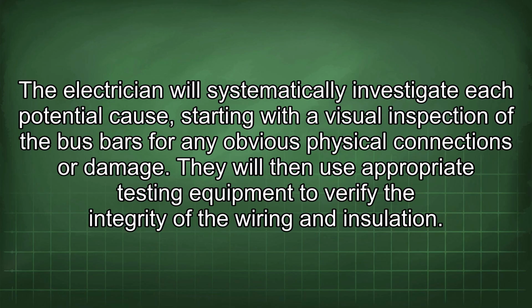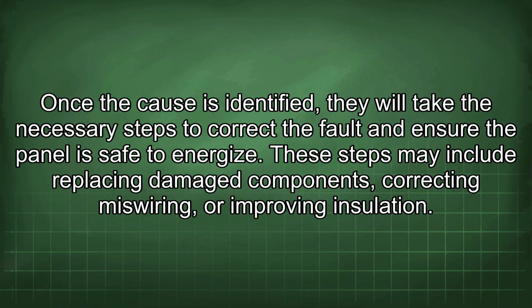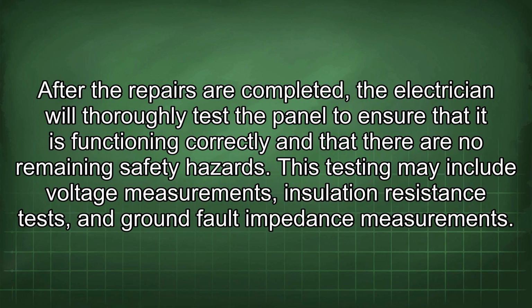The electrician will systematically investigate each potential cause, starting with a visual inspection of the bus bars for any obvious physical connections or damage. They will then use appropriate testing equipment to verify the integrity of the wiring and insulation. Once the cause is identified, they will take the necessary steps to correct the fault and ensure the panel is safe to energize. These steps may include replacing damaged components, correcting miswiring, or improving insulation. After the repairs are completed, the electrician will thoroughly test the panel to ensure that it is functioning correctly and that there are no remaining safety hazards. This testing may include voltage measurements, insulation resistance tests, and ground fault impedance measurements.